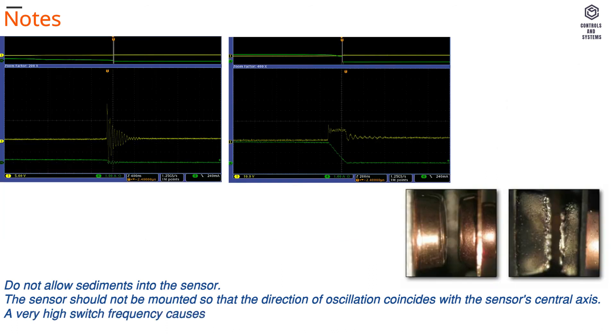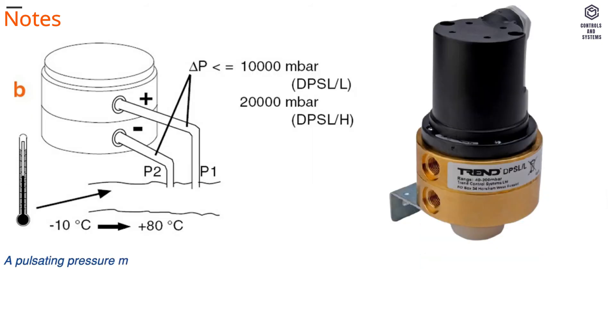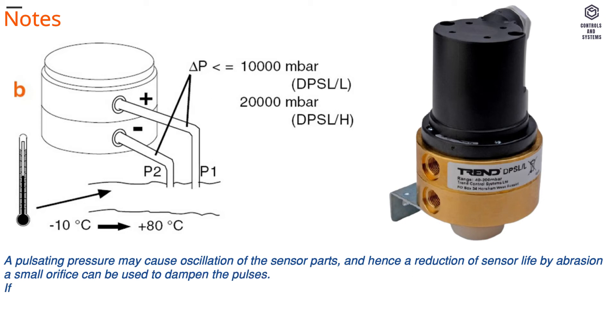A very high switch frequency causes the contacts to heat and hence reduces contact life. A pulsating pressure may cause oscillation of the sensor parts, and hence a reduction of sensor life. By abrasion a small orifice can be used to dampen the pulses.